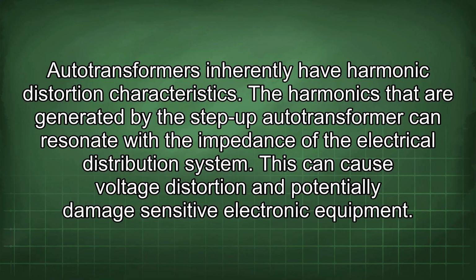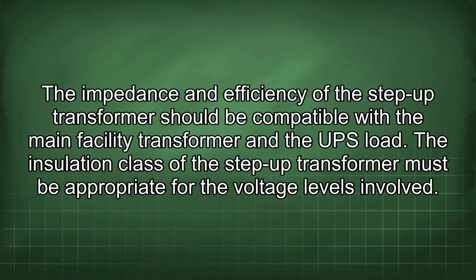Autotransformers inherently have harmonic distortion characteristics. The harmonics that are generated by the step-up autotransformer can resonate with the impedance of the electrical distribution system. This can cause voltage distortion and potentially damage sensitive electronic equipment. The impedance and efficiency of the step-up transformer should be compatible with the main facility transformer and the UPS load. The insulation class of the step-up transformer must be appropriate for the voltage levels involved.